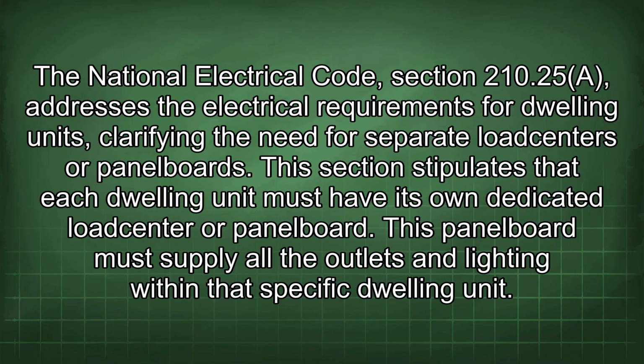The National Electrical Code, Section 210.25(A), addresses the electrical requirements for dwelling units, clarifying the need for separate load centers or panel boards. This section stipulates that each dwelling unit must have its own dedicated load center or panel board. This panel board must supply all the outlets and lighting within that specific dwelling unit.